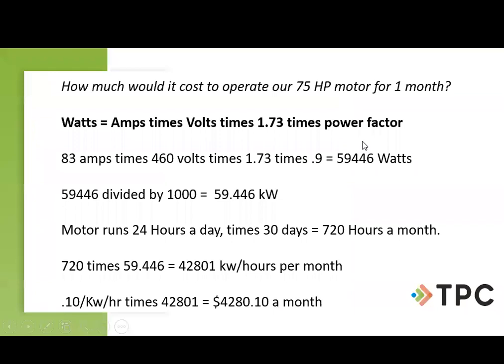Let's see how much it would cost to run that motor for a month. And so what do we have to do? We're going to use this formula: our amps times our volts. We've got to get 1.73 in there because it is three phase, and then our power factor. So we have the lower amps because we are using the higher voltage. We put in 1.73, the square root of 3, because it is three phase, and then 0.9. So that gives us this many watts.